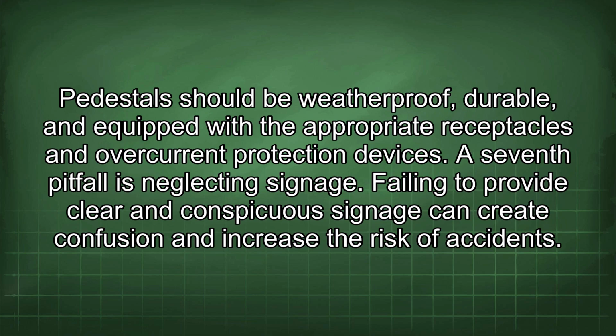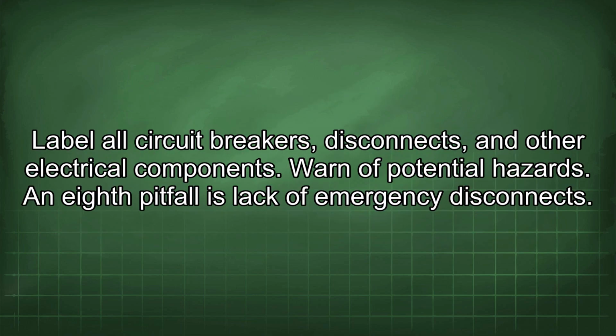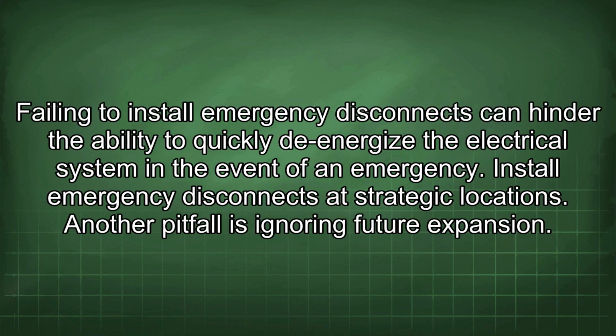A seventh pitfall is neglecting signage. Failing to provide clear and conspicuous signage can create confusion and increase the risk of accidents. Label all circuit breakers, disconnects, and other electrical components. Warn of potential hazards. An eighth pitfall is lack of emergency disconnects. Failing to install emergency disconnects can hinder the ability to quickly de-energize the electrical system in the event of an emergency. Install emergency disconnects at strategic locations.